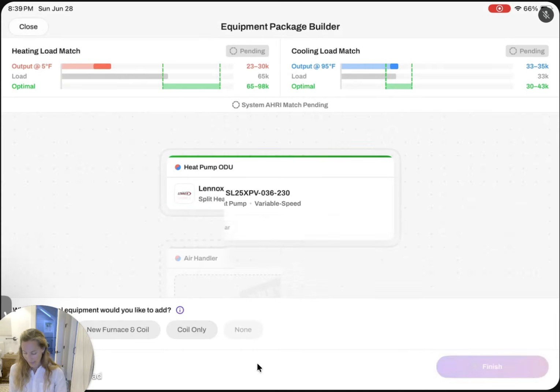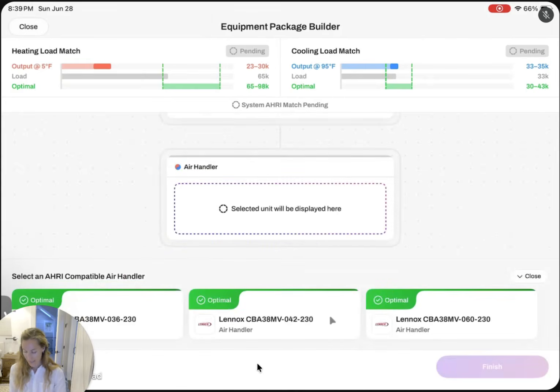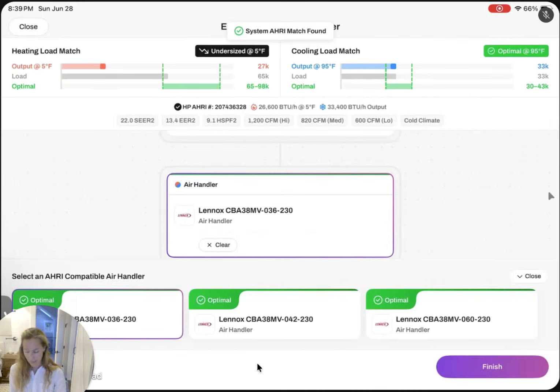We're going to add an air handler. This is going to show us the matching air handlers in our Pricebook. We're going to pick one that results in an optimally sized system. A couple things that I want to point out. Number one, we're sizing this to cooling. We want to see a nice green optimal badge here, and sure enough, we do. The heat pump has 33,000 BTUs cooling capacity. Our load is 33,000. We're falling right in the Manual S range.